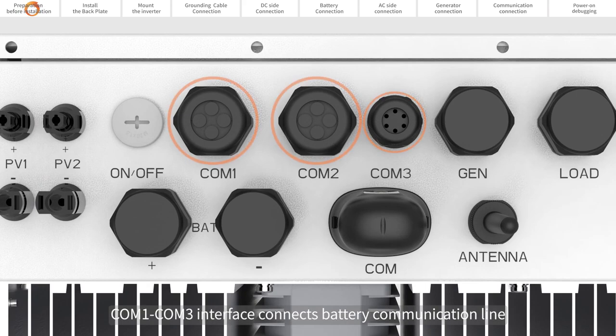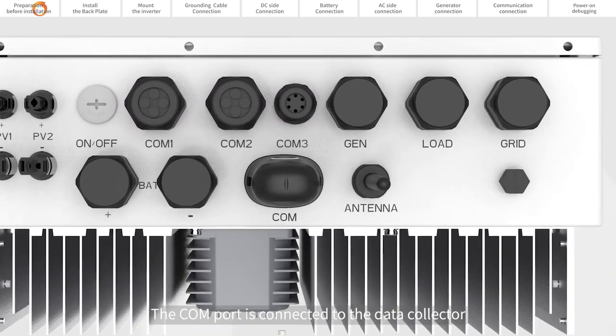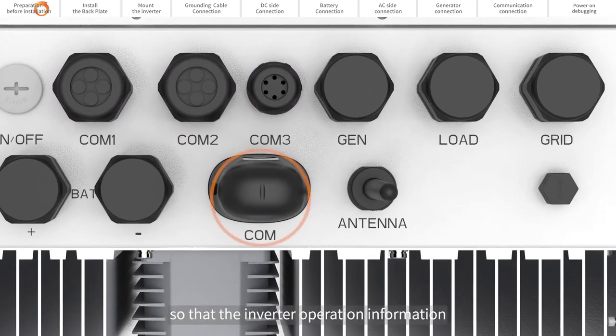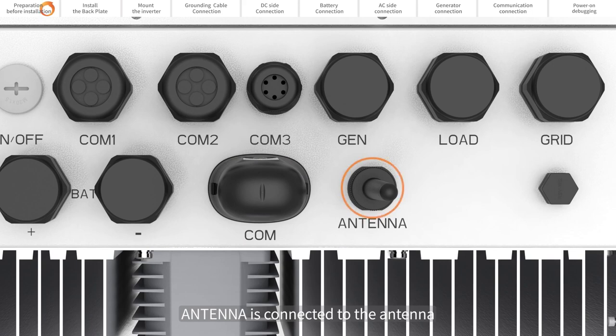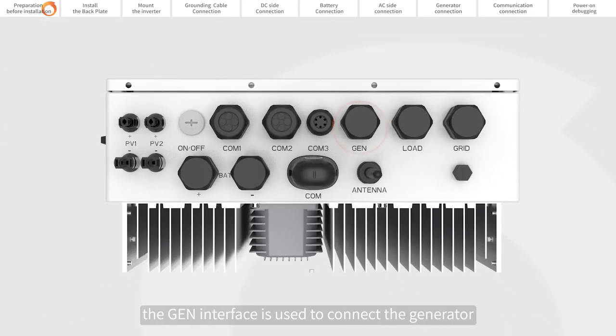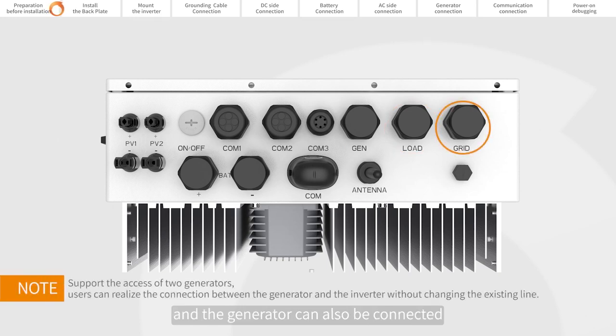The COM1 and COM3 interfaces connect the battery communication line, CT line, parallel line, and generator communication line. The COM port is connected to the data collector so that the inverter operation information can be uploaded to the Solis Cloud platform. The antenna port connects the antenna to enhance the Bluetooth signal. The generator interface is used to connect the generator. The load is used to connect the backup load. The grid is used to connect to the grid, and the generator can also be connected to the grid port through the automatic transfer switch.